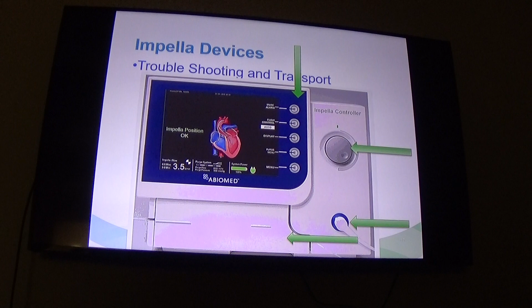So here's the actual Impella controller insertion point. That's where, when you're going, make sure that that's in place. Otherwise, the whole device won't work. And also, when you're transferring, this is the first thing to go into the new device. The reason is that this piece right here will tell the new device all the current settings. So it'll just restart when you transfer the patient right onto those previous settings.